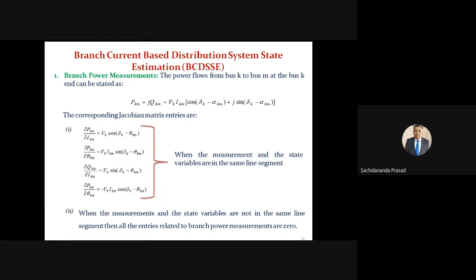Therefore, we use the branch current based distribution system state estimation algorithm at the distribution level for estimation purposes. These are the mathematical expressions related to state estimation in the distribution system, and this is the algorithm we use. We use the WLS method for the estimation technique, but here the variables we have chosen are branch current magnitude and angle, not voltage magnitude and angle, because with branch current magnitude and angle, you can also estimate the rest of the quantities of interest in the system.